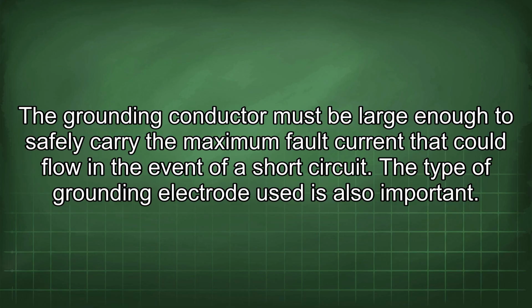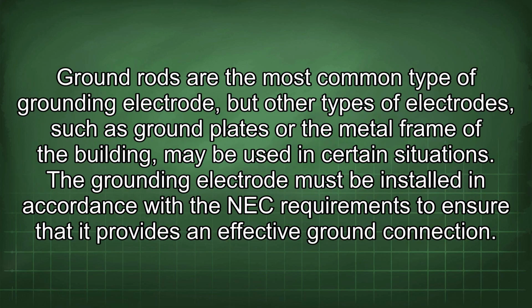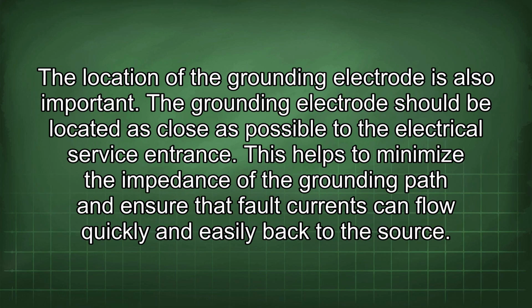The type of grounding electrode used is also important. Ground rods are the most common type of grounding electrode, but other types of electrodes, such as ground plates or the metal frame of the building, may be used in certain situations. The grounding electrode must be installed in accordance with the NEC requirements to ensure that it provides an effective ground connection. The location of the grounding electrode is also important.